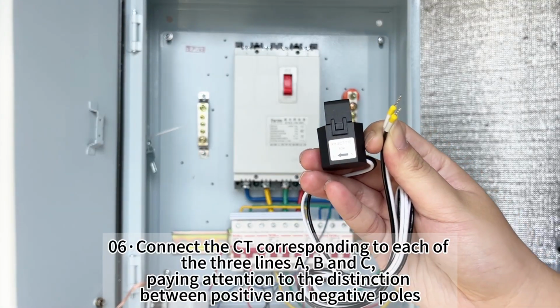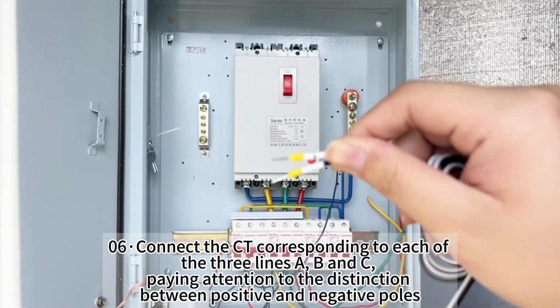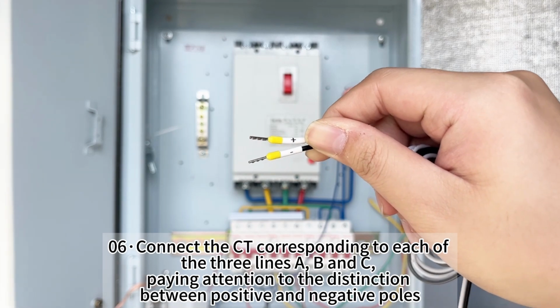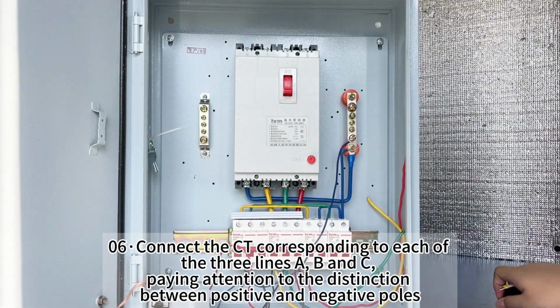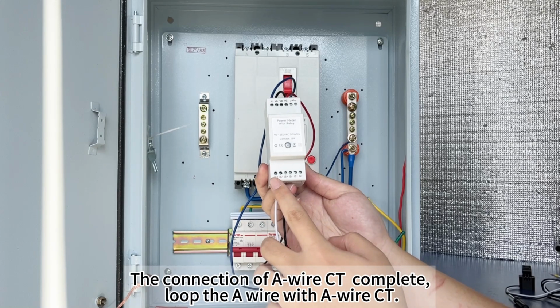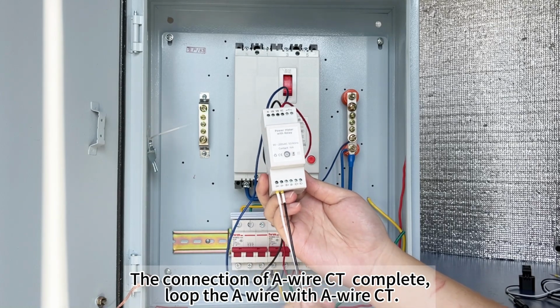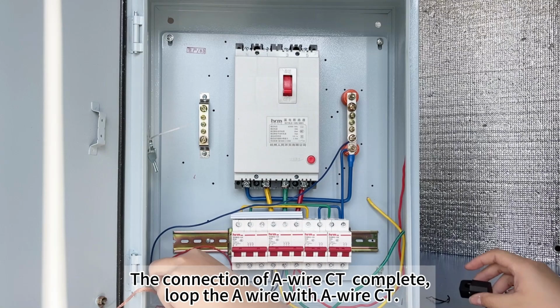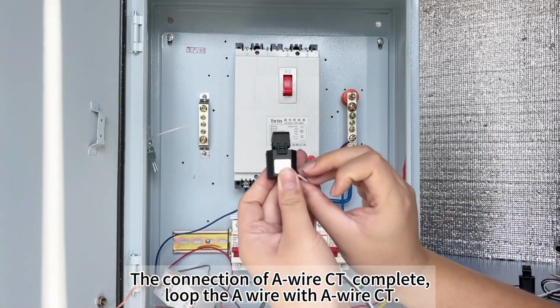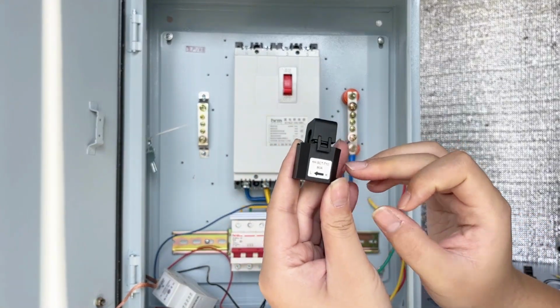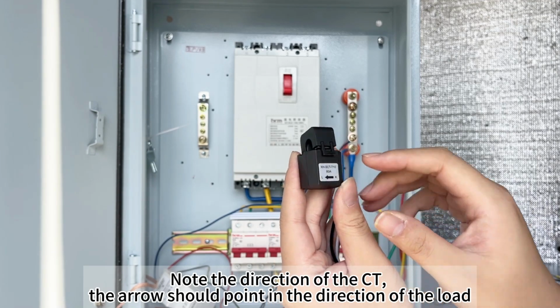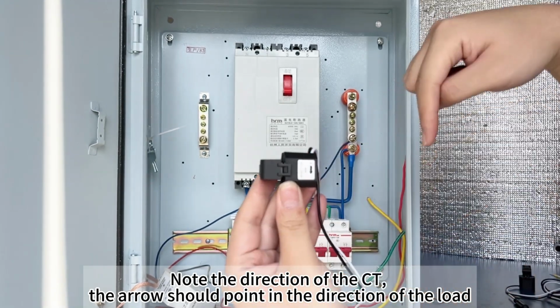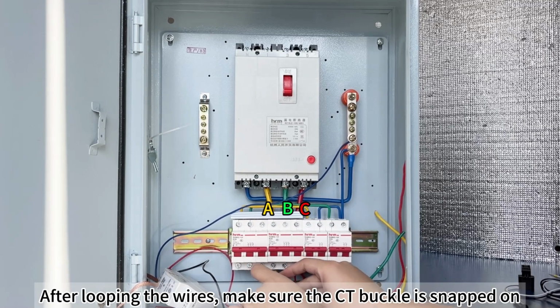Connect the CT corresponding to each of the three lines A, B, and C, paying attention to the distinction between positive and negative poles. The connection of A wire CT: loop the A wire with the A wire CT. Note the direction of the CT. The arrow should point in the direction of the load. After looping the wires, make sure the CT buckle is snapped.